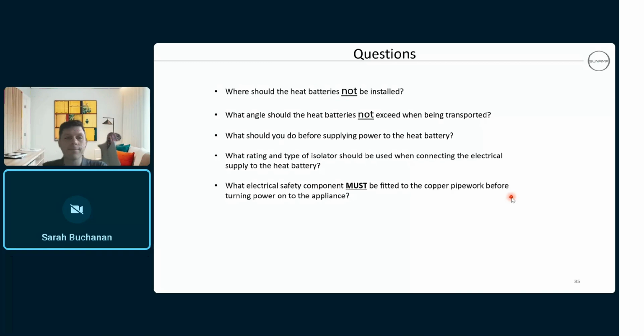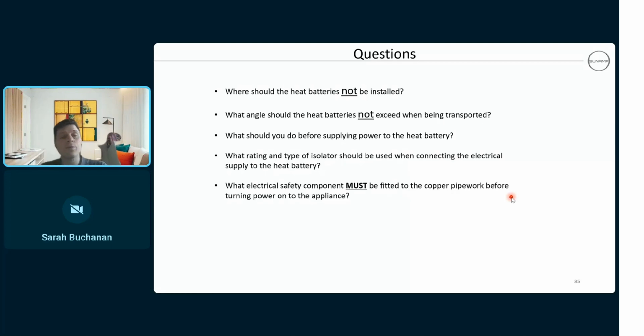And another one asking, are you able to install two heat batteries in parallel with one heat pump supplying both of them? Yeah, you can do. The problem you're going to have is, will the heat pump be able to keep up with the demand? With two heat batteries, your timing cycle for the heat pump would probably have to stay on for longer, because you're heating two appliances. You can do it, but it might have a negative effect on the heating system. So you might have to have the hot water come on at, like, 2 in the morning and be ready for the heating to come on at, say, 6 o'clock in the morning for the customer.